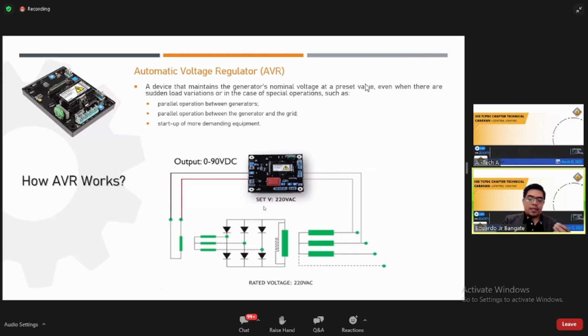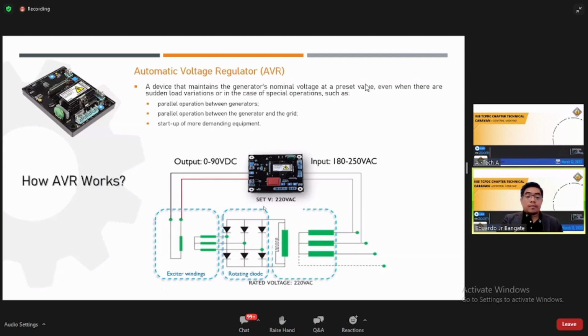You have here, let's say it has an output of 0 to 90 volts DC and an input of 180 to 250 volt AC. Once again, this is the exciter winding for the generator. This is a generator, okay? This one is the rotating diode. I hope everybody knows how to test a diode. You have to test the forward bias and reverse bias to determine if the diode is working fine or not. Anyhow, and this is the generator windings. Now let's try to rotate the generator.